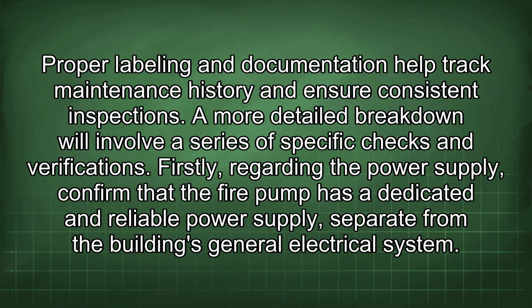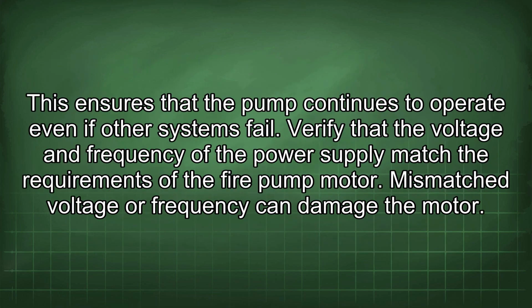A more detailed breakdown will involve a series of specific checks and verifications. Firstly, regarding the power supply, confirm that the fire pump has a dedicated and reliable power supply, separate from the building's general electrical system. This ensures that the pump continues to operate even if other systems fail. Verify that the voltage and frequency of the power supply match the requirements of the fire pump motor. Mismatched voltage or frequency can damage the motor.